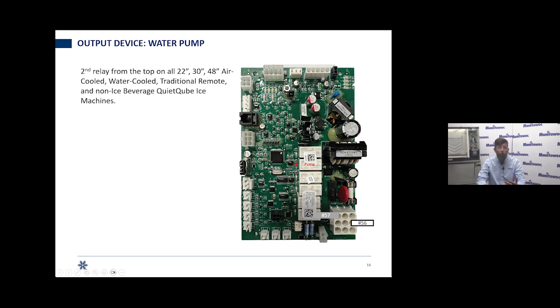But again, we're in freeze now. That's when the water pump is supposed to run. Well, what we're looking for at this point is water to be over this evaporator. Well, I've got water in the trough. How do I know that? Well, I saw my input lights. I saw with a working display. So I saw my water probe lights in the board are lit. I see that water is sensing. I even put my finger in that trough. I've got water and I'm in freeze. How? Because I've got a working display and real-time data told me I'm in freeze.